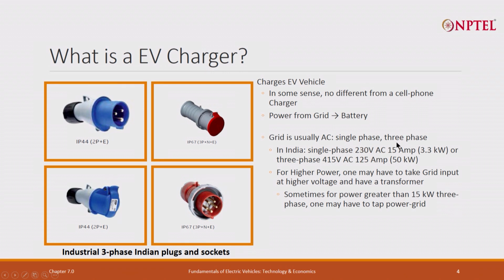Now, the first question is: the grid is usually AC, either single phase 230 volts or you can use 3 phase 440 volts. In India, single phase 230 volt AC is available everywhere, with 15 amperes available, though we normally use 5 amperes with that small plug. But 15 amperes is available too - for example, our air conditioners, washing machines, and some refrigerators use 15 amperes with a slightly bigger plug. So you can use 5 ampere or 15 ampere outlets, and 15 amperes will give you 3.3 kilowatts, or you can use 3 phase AC at 415 volts and up to 125 amperes, giving you 50 kilowatts.